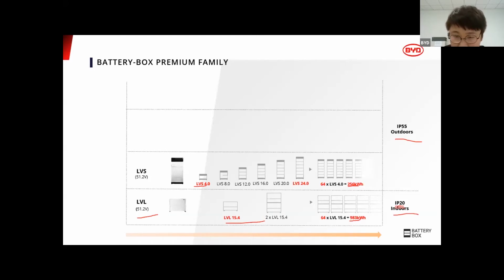So 0 means no resistance to any water, so you have to put the battery in the garage, under a shed, somewhere it never reaches any water. But for most residential grid-tie systems, with the new Australian battery installation standard, there's no way you can put the batteries inside the house anymore.